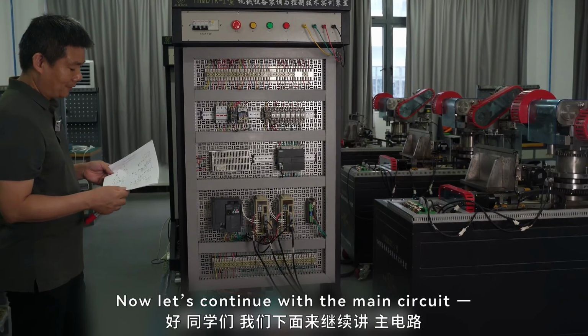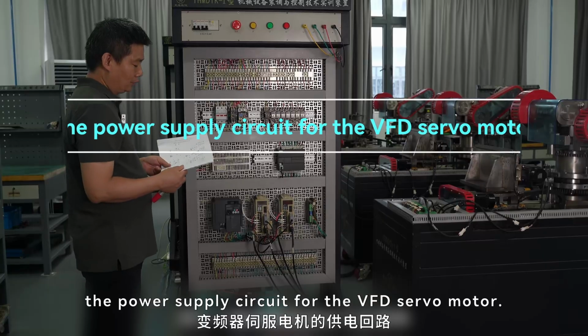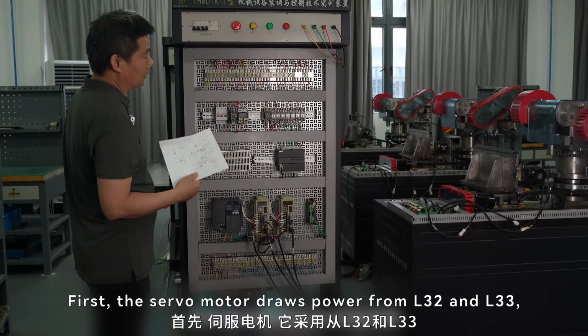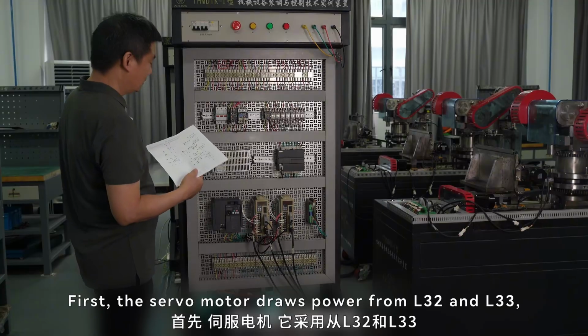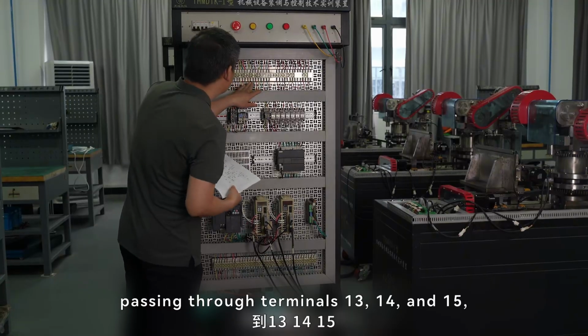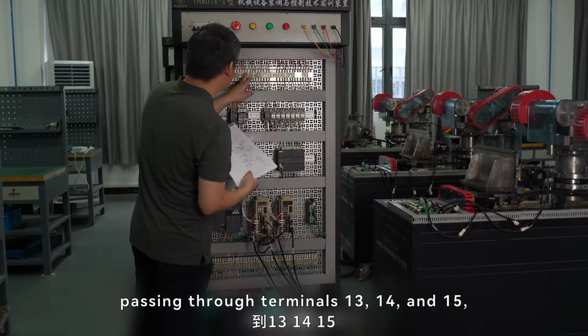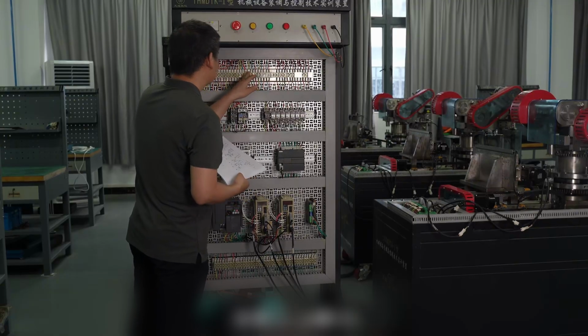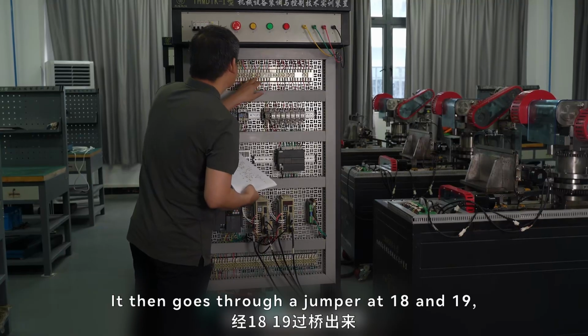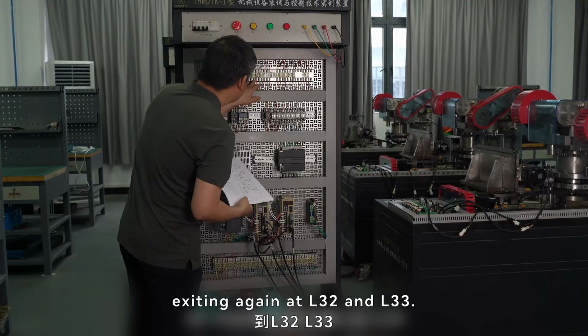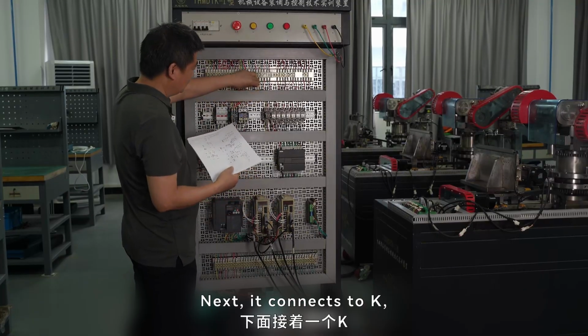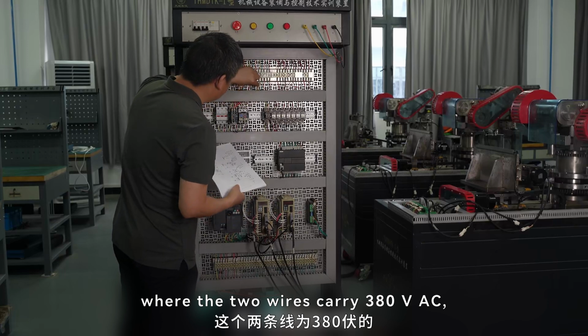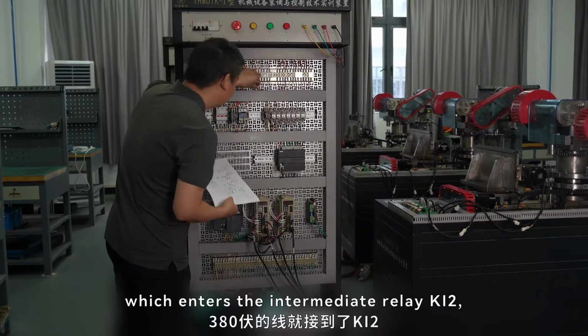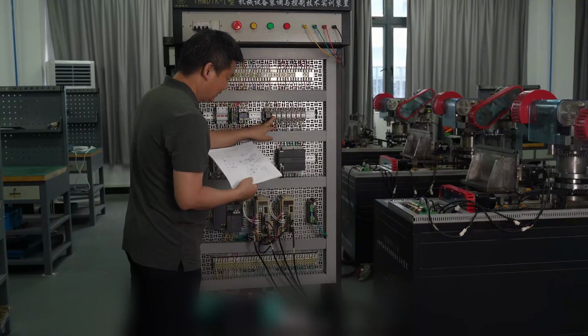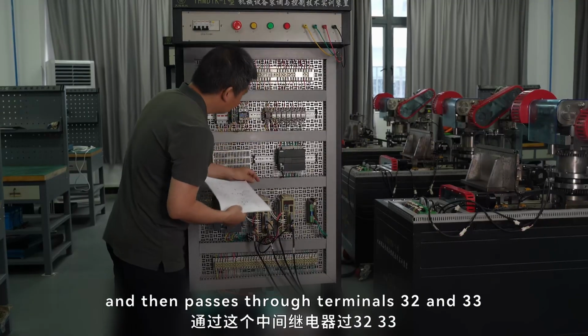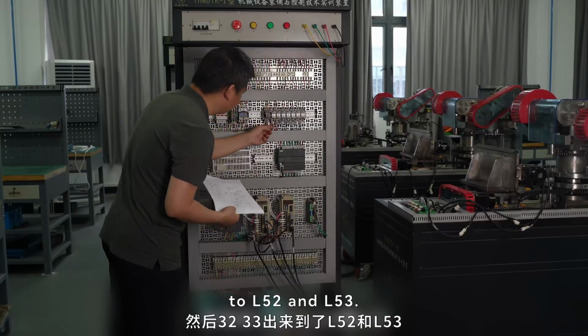Now let's continue with the main circuit, the power supply circuit for the VFD servo motor. First, the servo motor draws power from L32 and L33, passing through terminals 13, 14, and 15, and branching to this point. It then goes through a jumper at 18 and 19, exiting again at L32 and L33. Next, it connects to K, where the 2 wires carry 380 volts AC, which enters the intermediate relay Ki2, and then passes through terminals 32 and 33 to L52 and L53.